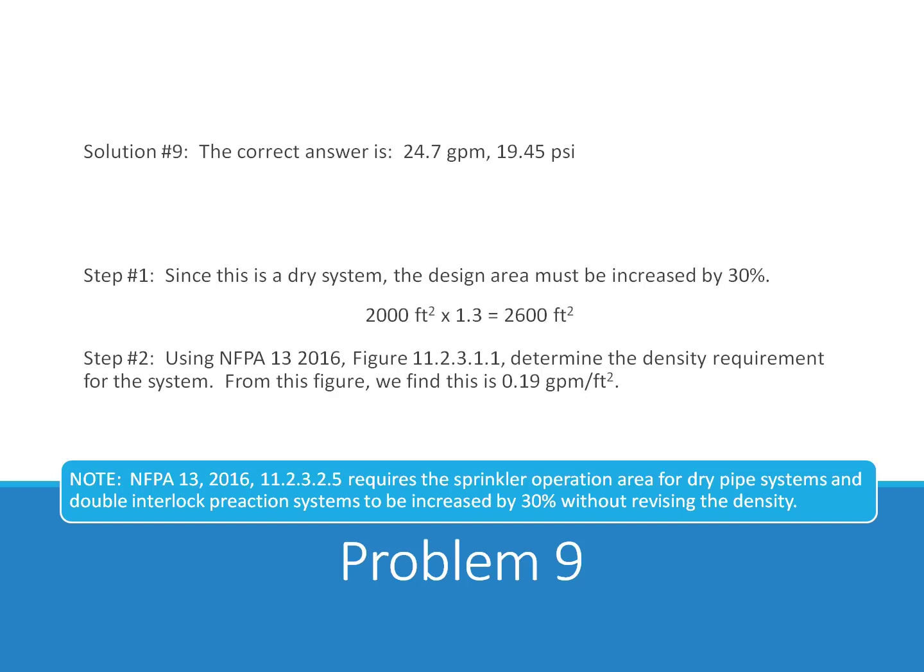Playing Jeopardy, the solution to problem number 9, the correct answer is 24.7 gallons per minute at 19.45 PSI. Step 1. Since this is a dry system, the design area must be increased by 30%. So if we had a square footage of 2,000 square feet, we multiply that times 1.3, that will give us 2,600 square feet.